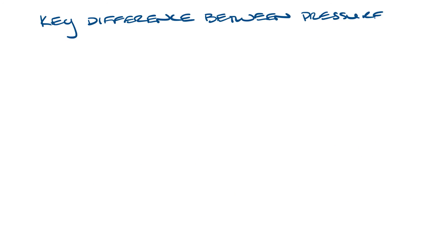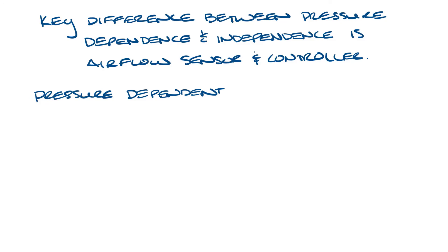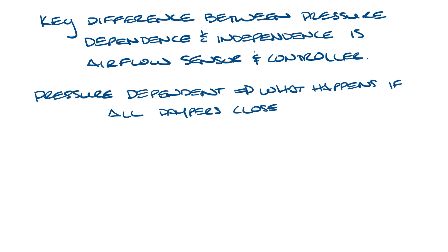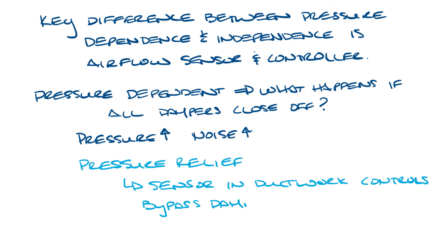Basically, the key difference between a pressure dependent and pressure independent VAV box is the flow sensor and the controller. One final thing about pressure dependence: what happens on the opposite situation — if all the boxes start closing off? Now there could be too much pressure in the system, which can cause a lot of noise and even blow duct work off of diffusers if they're not connected well. In this case, you need to have some sort of pressure relief. In many pressure dependent systems, you'll find a pressure sensor in the duct work that is measuring the duct pressure and either controlling a bypass damper, which will relieve duct pressure, or controlling fan speed, which will slow the fan down to reduce the pressure of the system.